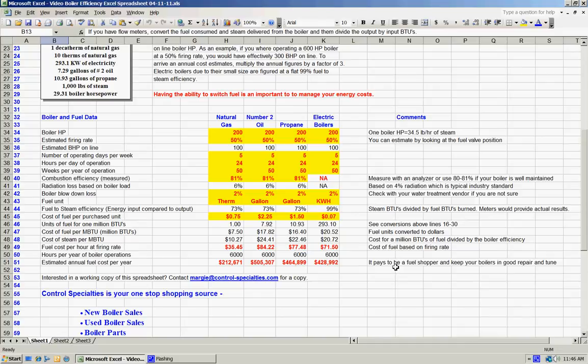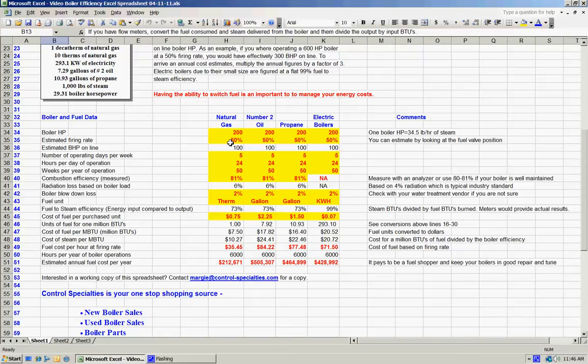If you take a look at line 34, what we've done is selected a 200 horsepower boiler in all cases, and we've had that 200 horsepower boiler firing at a 50 percent firing rate in all four examples, so that the estimated horsepower online would be line 36, 100 horsepower for each boiler. I selected those numbers. You can use the 100 horsepower example and ramp up to match whatever your specific boiler might be.